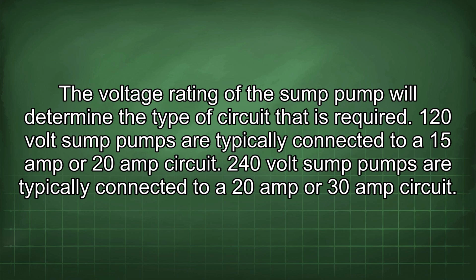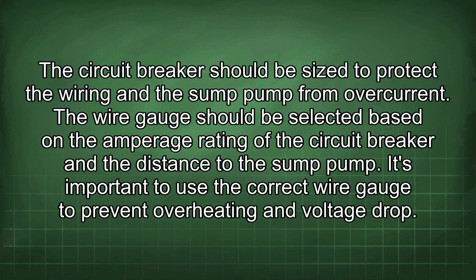120-volt sump pumps are typically connected to a 15 amp or 20 amp circuit. 240-volt sump pumps are typically connected to a 20 amp or 30 amp circuit. The circuit breaker should be sized to protect the wiring and the sump pump from overcurrent. The wire gauge should be selected based on the amperage rating of the circuit breaker and the distance to the sump pump. It's important to use the correct wire gauge to prevent overheating and voltage drop.